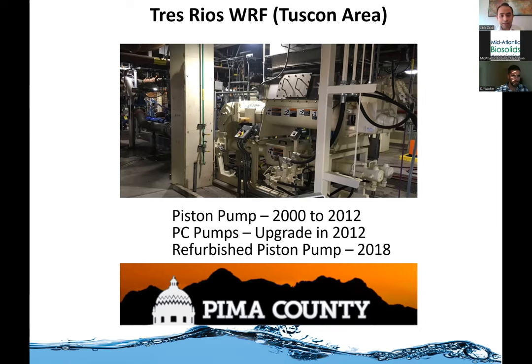And then what they did, they had our old pumps, which they stopped using in 2012. So they refurbished those piston pumps and reinstalled them in 2018. And then they ran piston pump and PC pump side by side to do this study, to find out if it was a good idea to switch from piston pumps to PC pump, or they should have stayed with piston pump. And also the main purpose of this study was to justify in front of their board that even for smaller or lighter applications, piston pumps make more sense economically and because it's more reliable and downtime is very, very low.